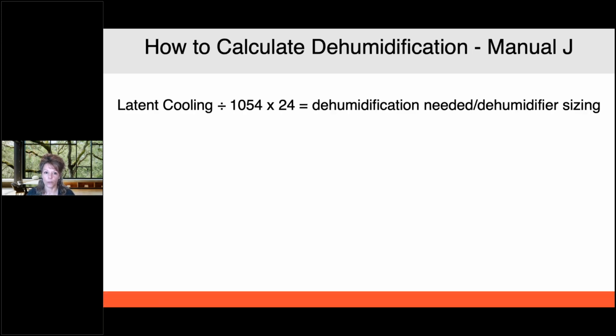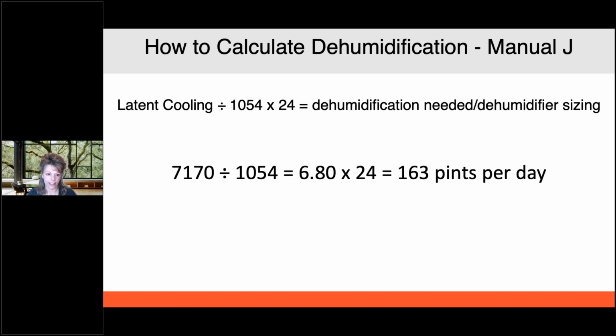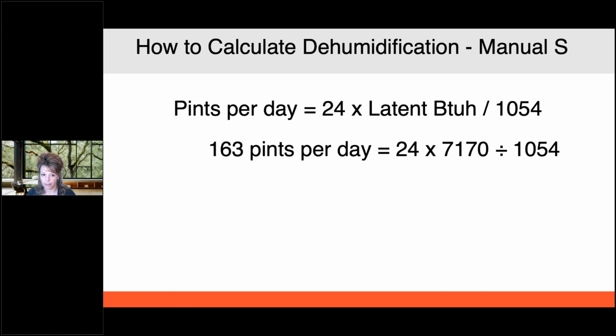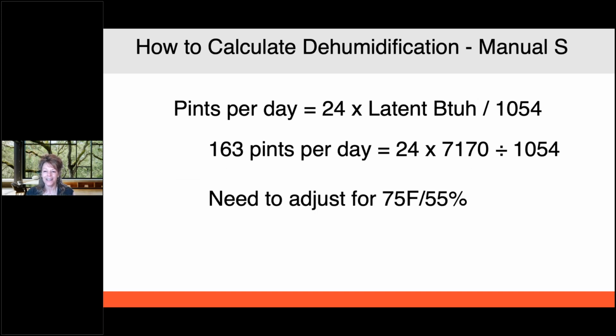Manual J gives you a calculation based on your Manual J loads. What it might look like here is my latent load is 7,170. It takes 1,054 BTUs to remove a pint, or a pound, of water. So we divide that, then multiply by 24 hours in a day, and that gives me about how much dehumidification I'm going to need. Then I have to figure out how much of the time my AC can handle that, and how much of the time I'm going to count on a dehumidifier. Manual S is very similar. The challenge with Manual S is that Manual J is 50%, Manual S is 55%.